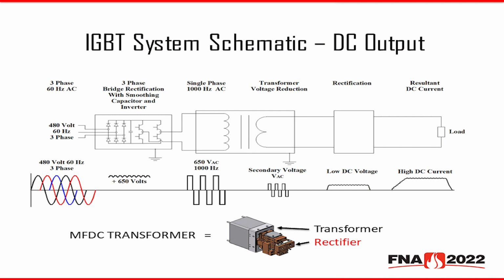It's also important to note that the losses in a system are proportional to the magnitude of current change. So in a secondary circuit where you have that high current power, which you need for heating, that high current power is also very inefficient. And so you want to make sure that that high current power is just used for heating and not for anything else.